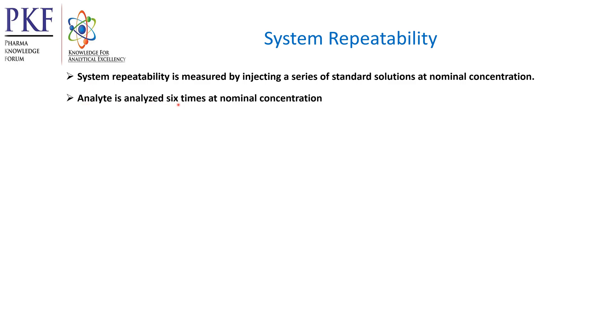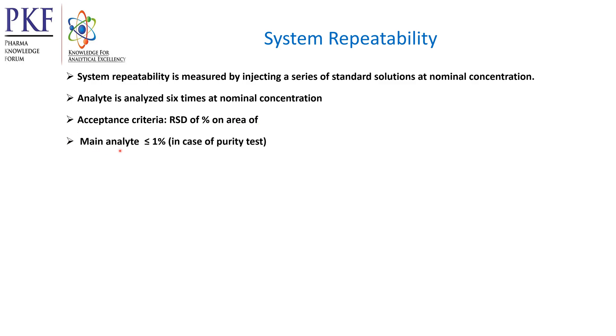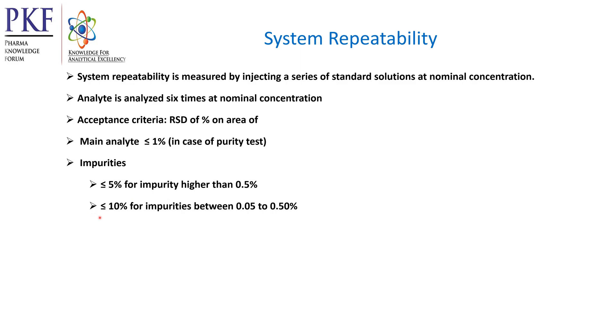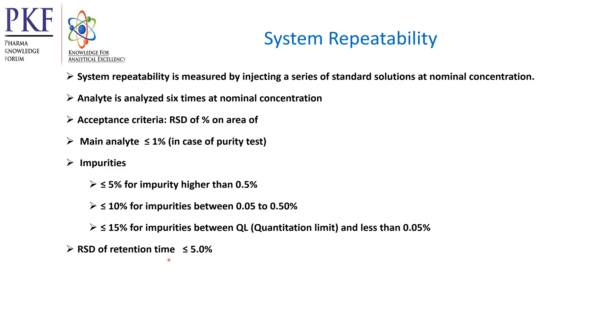The analyte is analyzed six times at nominal concentration. For acceptance criteria: RSD of area percent of mean analyte should be less than or equal to 1% for purity test by area normalization method. For impurity, RSD should be less than or equal to 5% for impurity higher than 0.5%, less than or equal to 10% for impurity between 0.05% and 0.50%, and less than or equal to 15% for impurity between quantitation limit and less than 0.05%. RSD of retention time must be less than or equal to 5%. RSD is not calculated for percentage area lower than the quantitation limit.